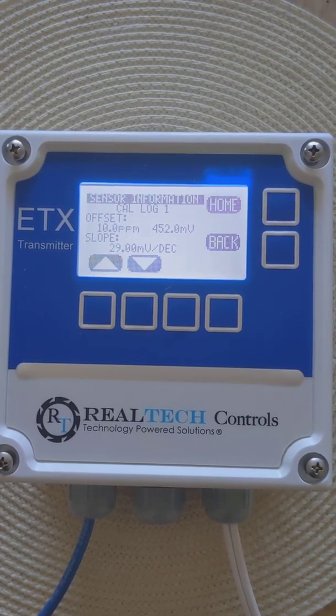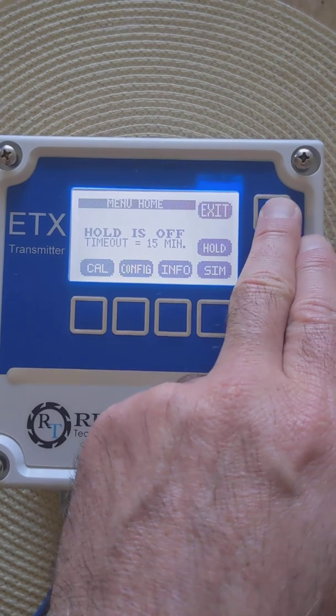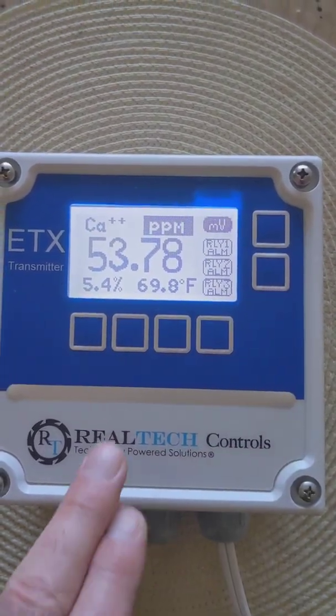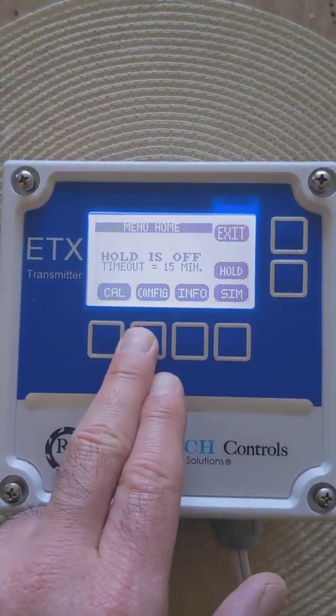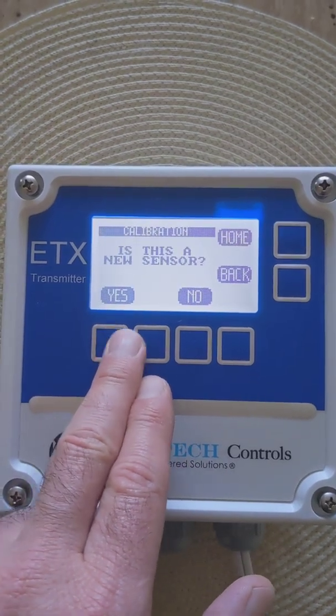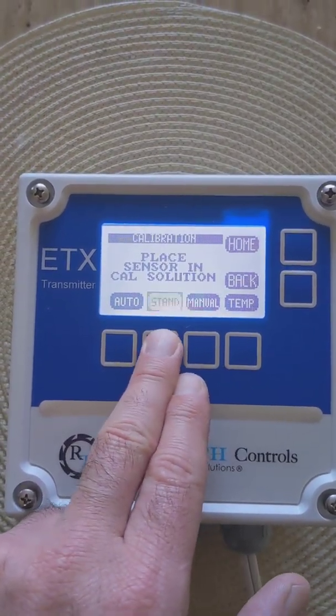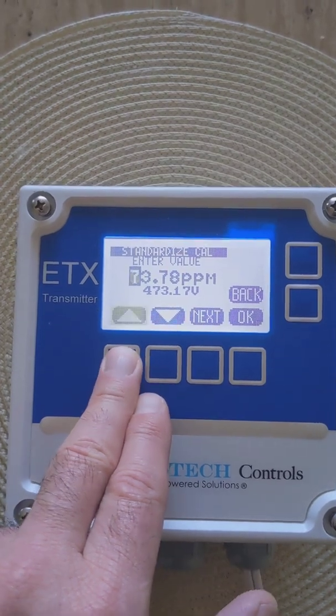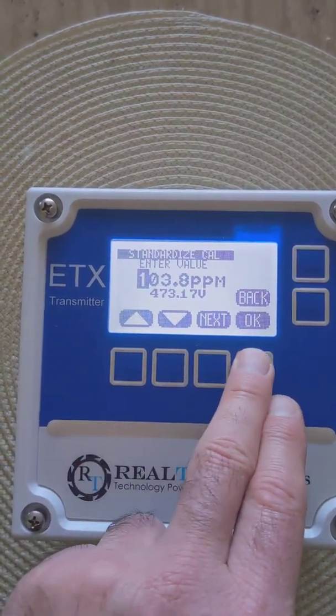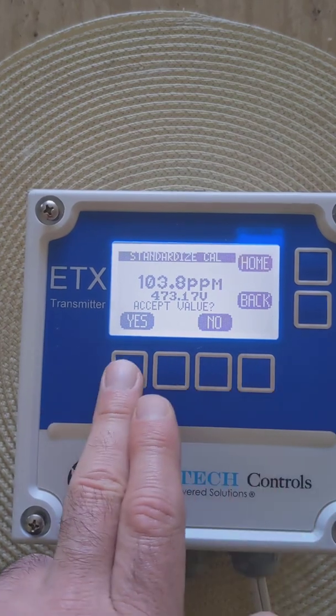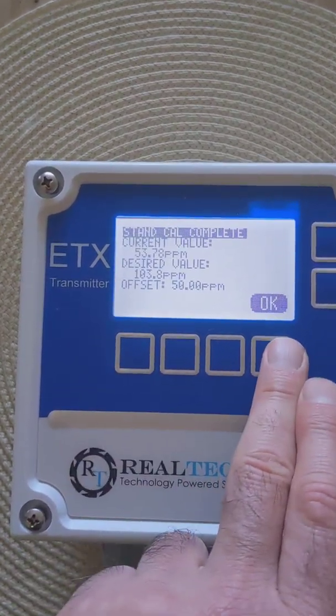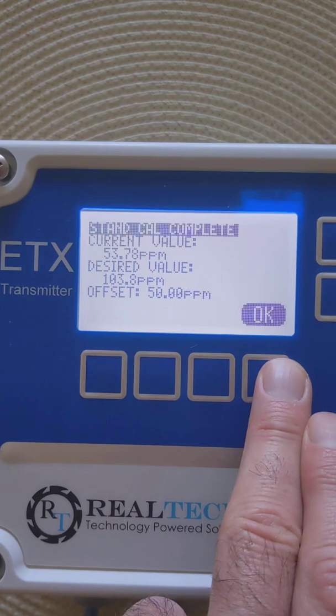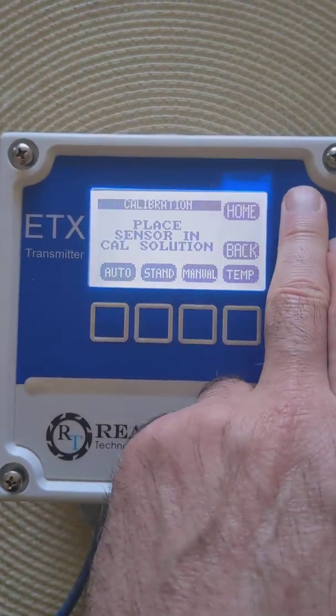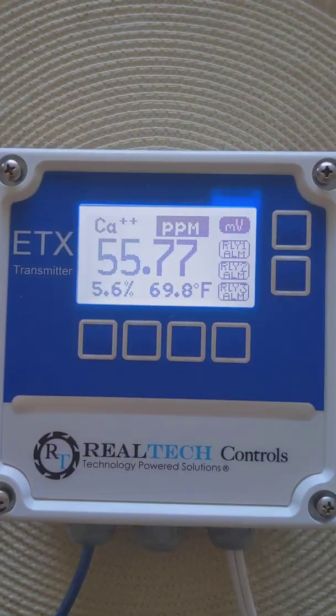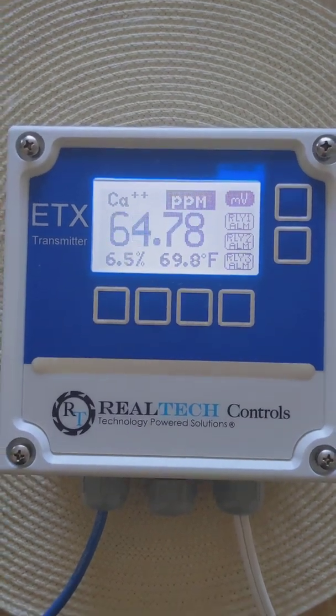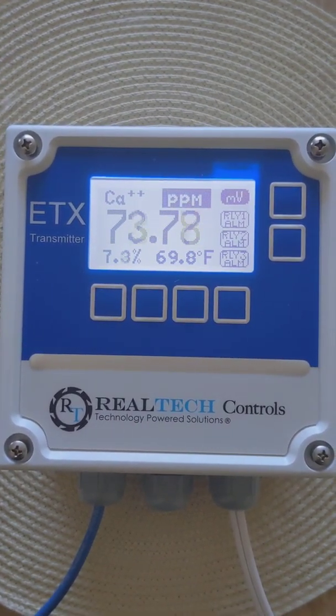So once I've recorded these values, for example, now I install the system and I want to calibrate it. So I go to Calibration. It's not a new sensor. I'm just going to do a single point calibration as per the other videos. And just for argument's sake, just calibrate that, accept the value, yes. That is the new values now that I entered in for the sensor. I push OK. I go back to home. So you see that that will change based on the calibration I now did.